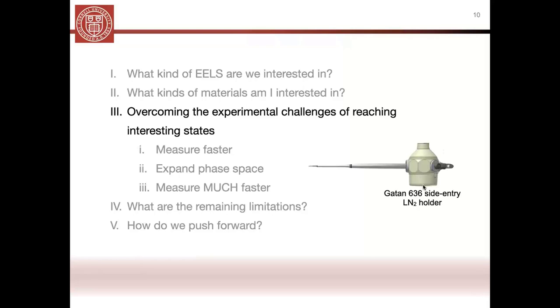That's where you put the cryogen. In this case, I'll be mostly talking about work with liquid nitrogen. Your sample sits out here at this thin tip that extends into the microscope. And so one thing that's inherent to all of these side entry cryo holders is that there's a big thermal gradient between the cryogenically cooled sample, the cryo Dewar on the outside, and then the rest of the warm microscope room.